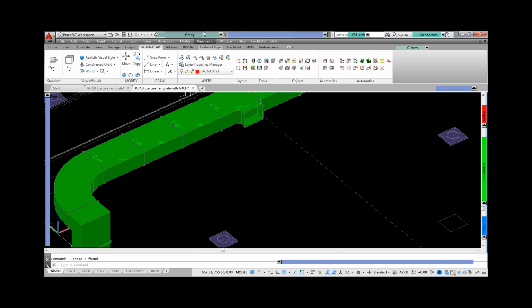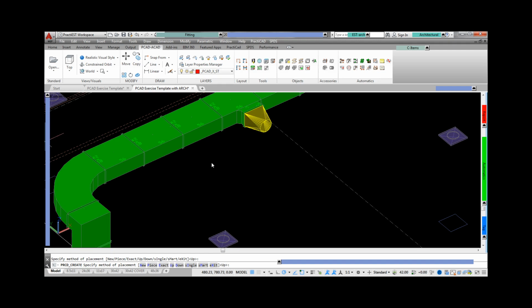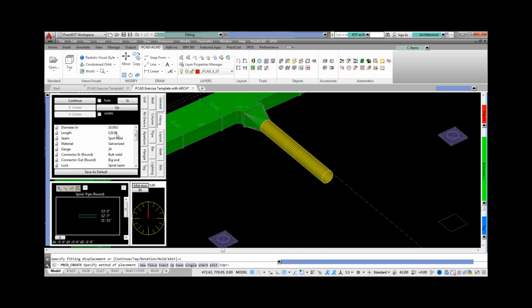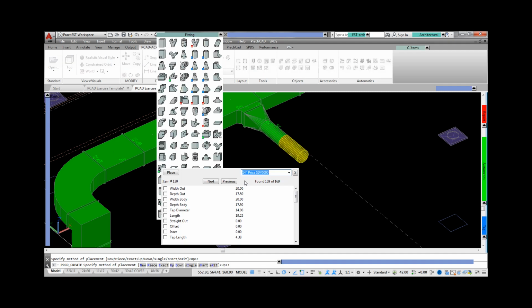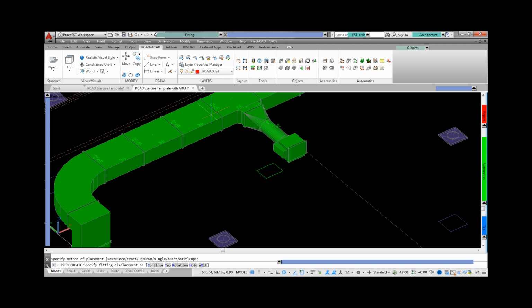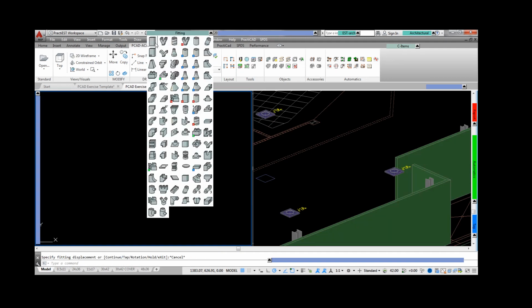Looking further into PractiCAD's intelligence, we will focus on this 56-inch TDF joint. Notice the fabrication level says label only. For this user, it means send to coil line. Notice as we change connections, it changes the length to slip and drive coil line joint. Then, if we change the length of the duct, the fabrication level switches to cut and label, which means now sent to plasma.